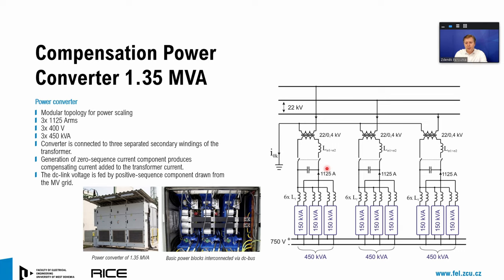Just a brief idea of how our converter looks. It is a three-phase converter where we are using a modular topology with fundamental building blocks with the rated power of 150 kVA, which makes easy scaling of our device possible. In our prototype we are operating three fundamental building blocks in parallel, and they are connected via an LCL filter to a secondary winding of the converter transformer.